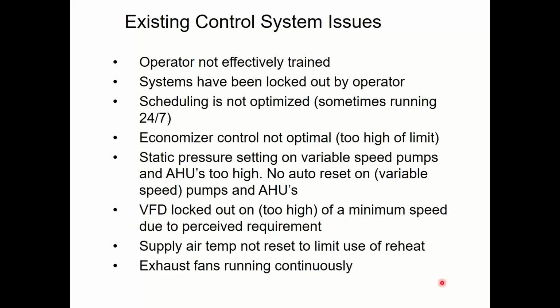They didn't want to go spend the effort to program it, especially on these small package systems like we're talking about today, because maybe you have 4 or 5 of these package systems, and maybe your company has 10 buildings like that, which means you now have 50 thermostats on the wall. And if you want to fix the scheduling, you got to go to 10 buildings and change 5 stats at each one, and maybe you just don't want to do that. Just a lot of effort, and you're just like, screw it. What do I care, right? There's a lot of people that don't put schedules in their home thermostat, and they pay that bill personally. So I told you how difficult it is to get somebody to schedule their building and schedule their thermostat.